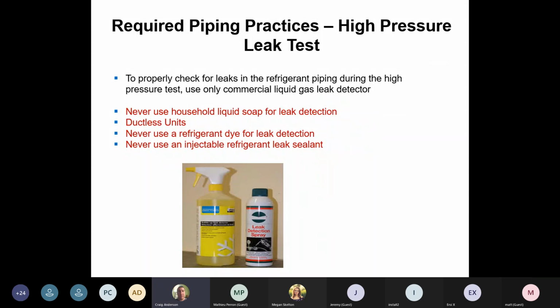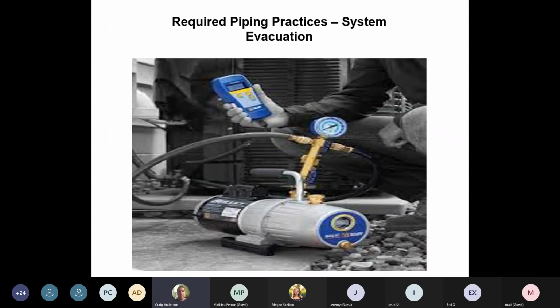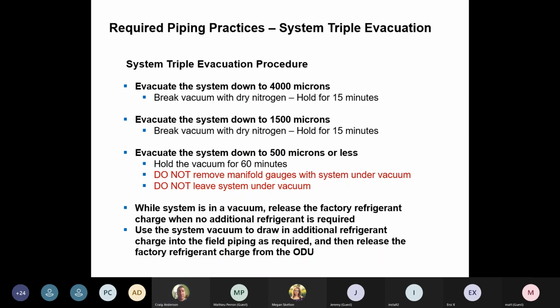So, system evacuation, this is the big thing. This is where we want to get the moisture out of the system. Three-step evacuation, it's been in the manuals for years. This is nothing new. This is what they've always recommended. We're trying to dry what's in the system. If that is dry and we got pure freon going through it, then our system is not contaminated.